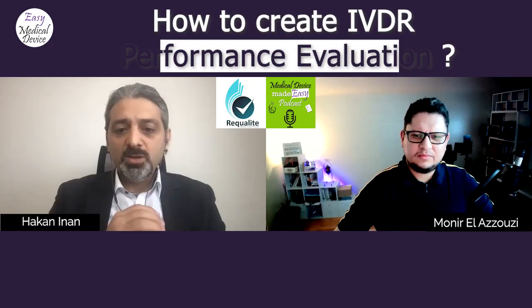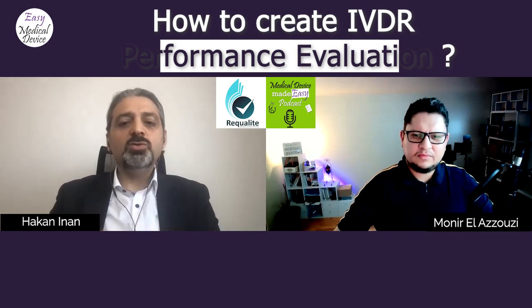And the third step: you have scientifically validated, and you have also proven that analytically your device is working well. At that stage, you don't need to work with patients because you just wanted to know whether the device is working well or not. But then the next step is that you have to show that the device is actually functioning in diabetes patients. So there you have to find the clinical data. There the clinical performance comes into the picture, and there the real-world data, where your device is used in clinical settings as intended. So this constitutes your clinical performance and goes into the clinical performance report.